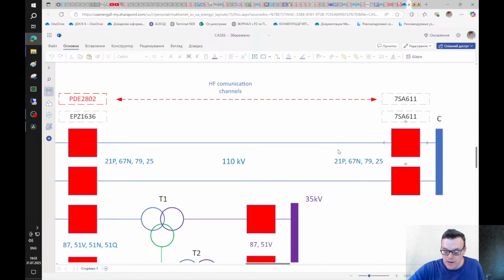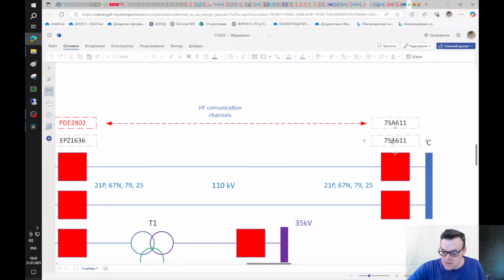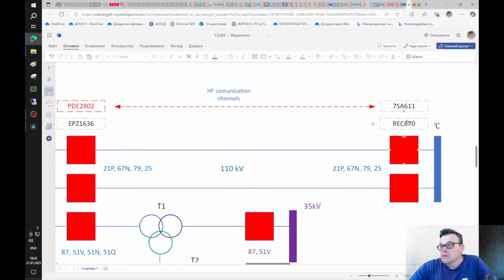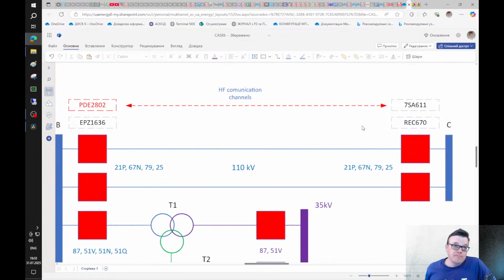We have here two parallel lines with the same protections at each side. From this side, a Siemens terminal 7SA611 and a BCU unit. The protection functions are distance protection that works only with multi-phase short circuits, ground overcurrent directional protection, automatic reclosing, and synchronized check.